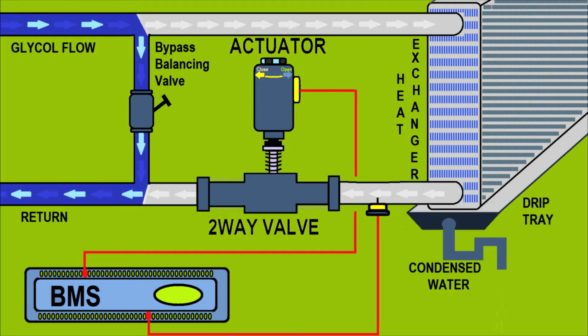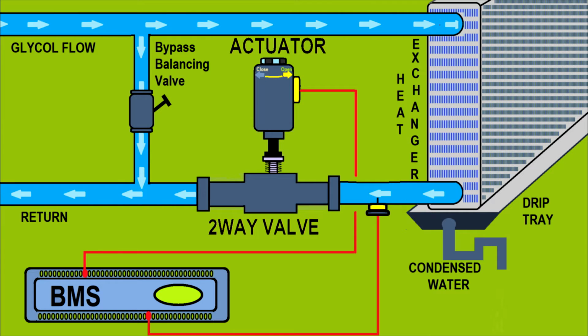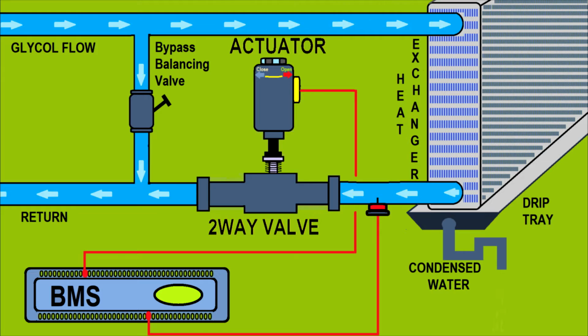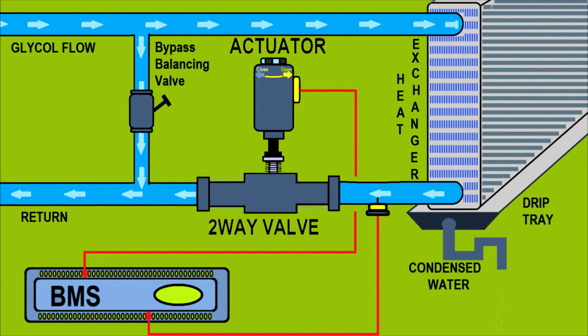Like for the heating, on a cooling situation, the same rules apply. You have an actuator which is proportional. It goes from 0 to 100%. You also have the bypass balancing valves. Imagine you have 20 heat exchangers, you have to make sure they all receive the appropriate quantity of glycol to cool the premises. These are things that have to be considered.